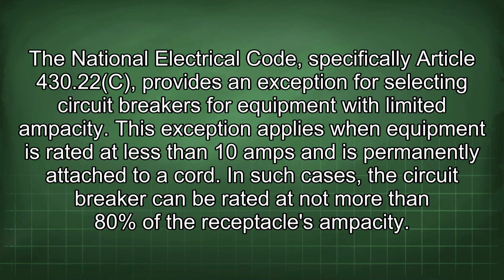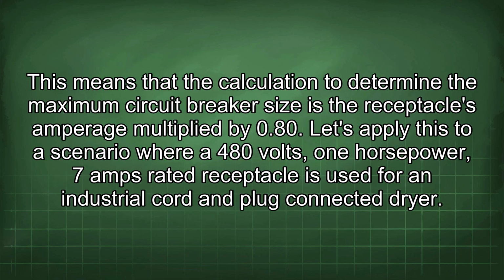The National Electrical Code, specifically Article 430.22(C), provides an exception for selecting circuit breakers for equipment with limited ampacity. This exception applies when equipment is rated at less than 10 amps and is permanently attached to a cord. In such cases, the circuit breaker can be rated at not more than 80% of the receptacle's ampacity. This means that the calculation to determine the maximum circuit breaker size is the receptacle's amperage multiplied by 0.80.